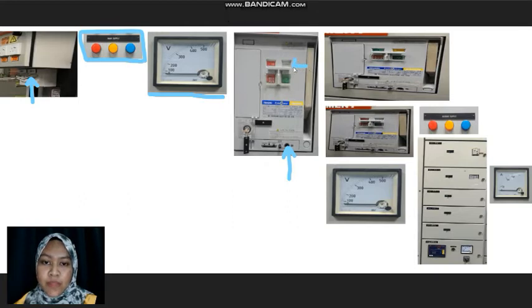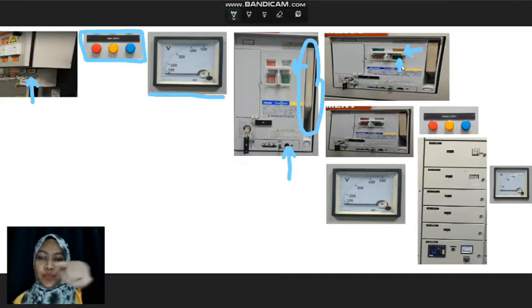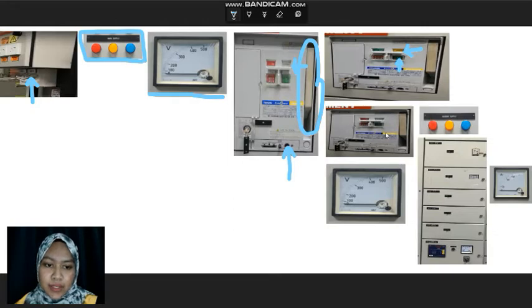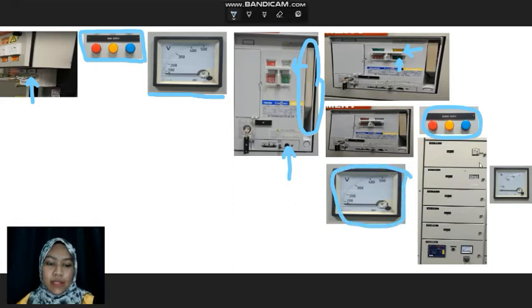In order to turn on the air circuit breaker, we must make sure that the coil is in charge position. But as we can see here, it is in discharge. So we use the charging handle here and pull it up and down a few times until the coil is in charge position. After that, we push the green button to turn on the air circuit breaker. After that, we check the bus bar supply and the voltage at the voltmeter.